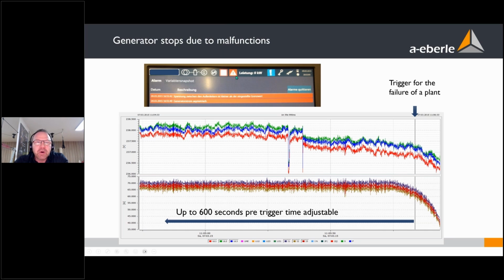Here, this is one story where a big generator stopped many times during one week, and we want to find out what the problem is. Often customers take an analyzer and measure the power quality. Is there a voltage dip or swell, or something with harmonics? Much easier is to tell the device: if the generator is working fine, we have 70 amps, and if the generator has some disturbance and stops, the current goes lower than our threshold, lower than 50 amps, then we have a problem.